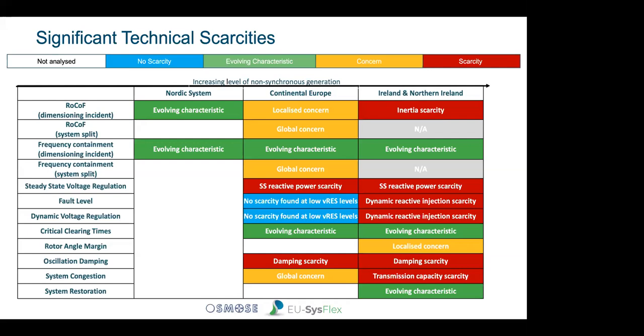It's important to note that while no dynamic voltage scarcity was identified in the continental system, there's a caveat: the analysis for continental Europe only considered the Polish system, which didn't have very high levels of non-synchronous generation in our scenarios. We anticipate that at higher levels of non-synchronous generation for Poland, there would be significant issues related to dynamic voltage control, similar to those identified for the Ireland and Northern Ireland power system, where the levels of RES we investigated were up to 70%.